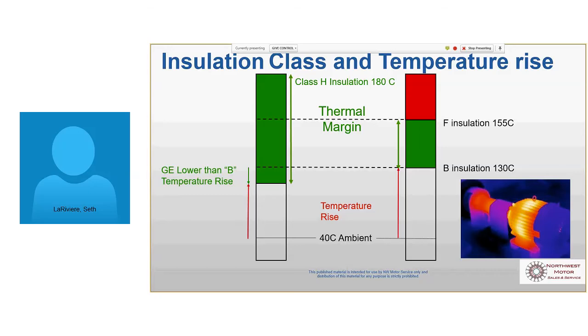You start off with this 40 degree C ambient. That's understood. That's just a given. NEMA assumes that all ambient temperatures are that. So then on top of that, you have the rise. So if you take 40 degrees and then 80 degrees C of rise, and they also throw in a 10 degree hot spot allowance in case you're not measuring the motor at its exact hottest point. There might be a little hotter temperature somewhere. They throw in 10 degrees of fluff. So you've got 40 plus the 10 is 50 plus the 80 is 130. So that gets us here to the 130 total insulation limit of that motor. But it actually can go up to 180. So is that kind of clear? Because if there's one thing I want everybody to get today, it's that story. Because that's why people buy these motors. That's the reason.